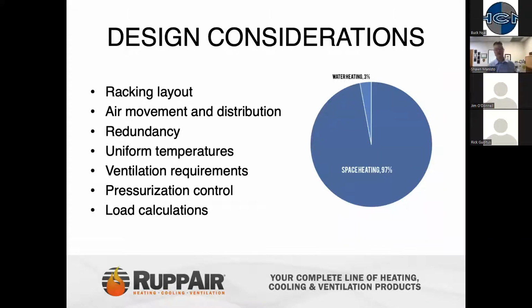Other design considerations as you start looking at the HVAC system for these warehouses are the racking layout, how the racking layout exists in that facility. Air movement and distribution, making sure we have good coverage throughout the facility. Is redundancy needed or wanted? So maybe you have a small facility where one heating system or one fan could cover it, but maybe you want to look at some redundancy characteristics. Uniform temperatures, how can you get uniform temperatures throughout the entire building? Ventilation requirements, what's needed. Pressurization control, why it's important. And then understand how you take all these things and develop a load, or basically a heat calculation, for what's required to heat these boxes.